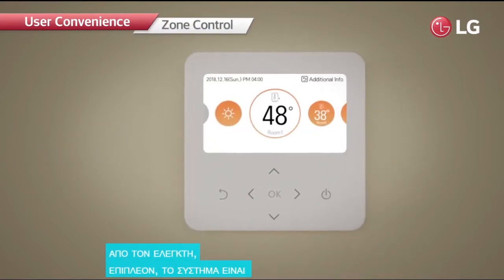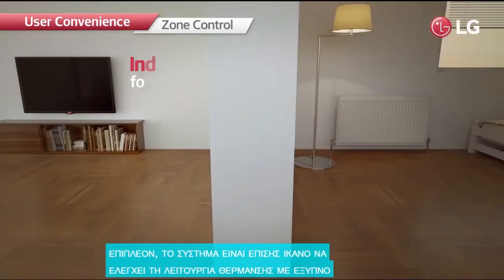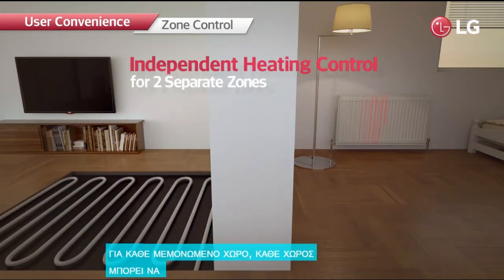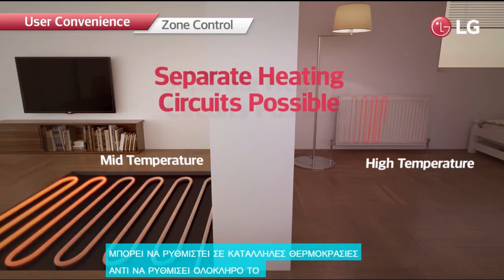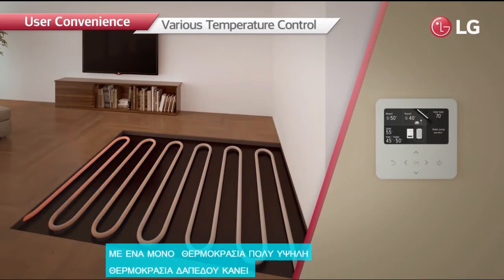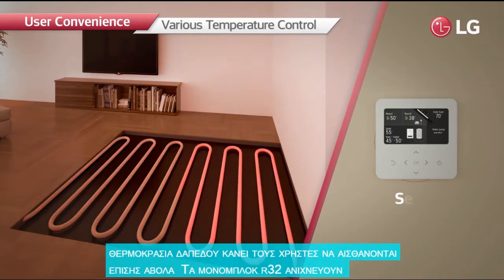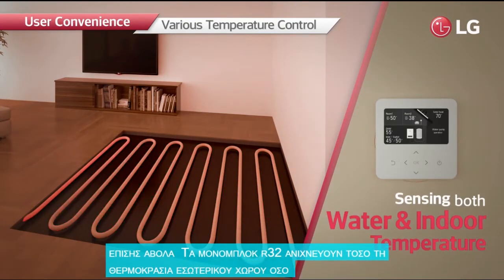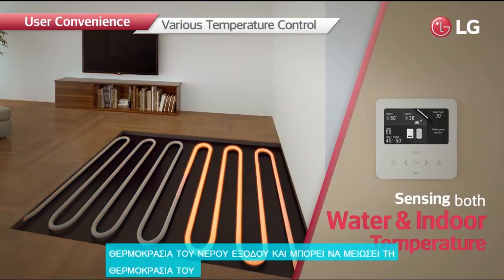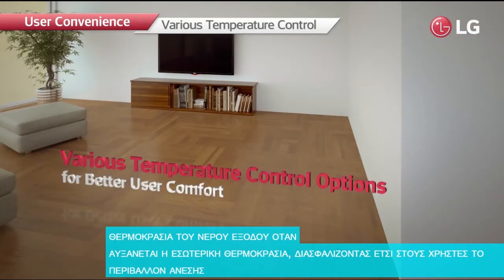The system is also capable of controlling heating operation in a smart way for each individual space. Every space can be set to suitable temperatures rather than setting the entire floor with a single temperature. As the R32 Monoblock senses both indoor temperature and leaving water temperature, it can reduce the leaving water temperature when indoor temperature rises, ensuring a comfortable environment.